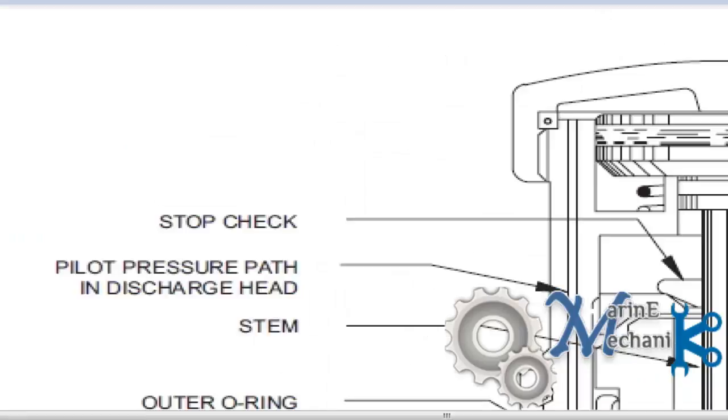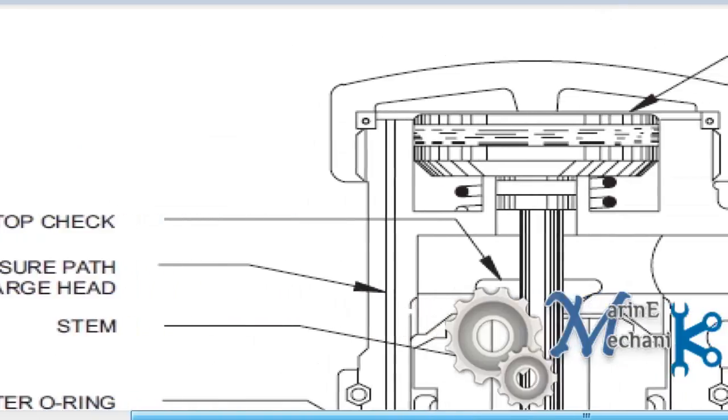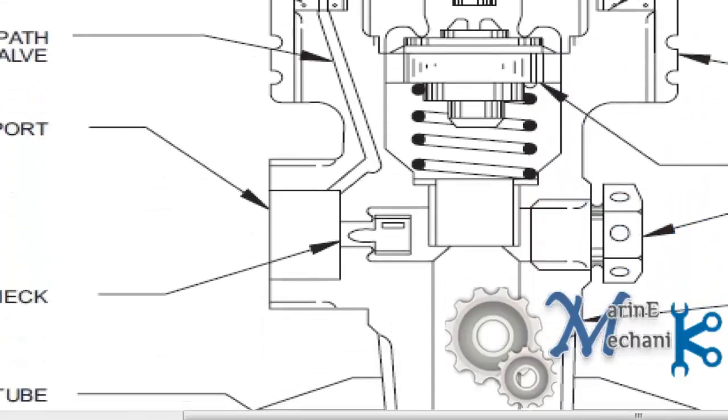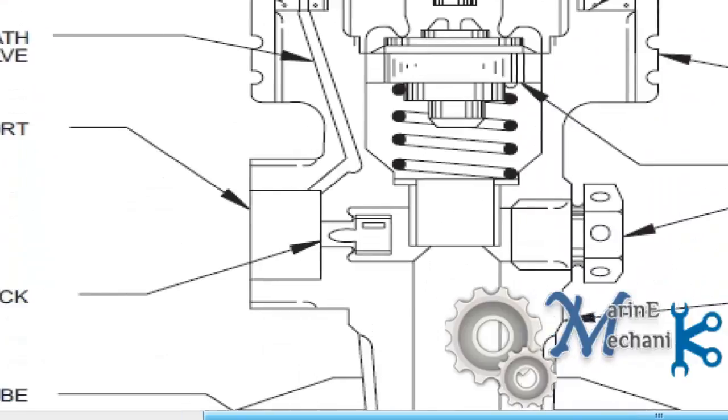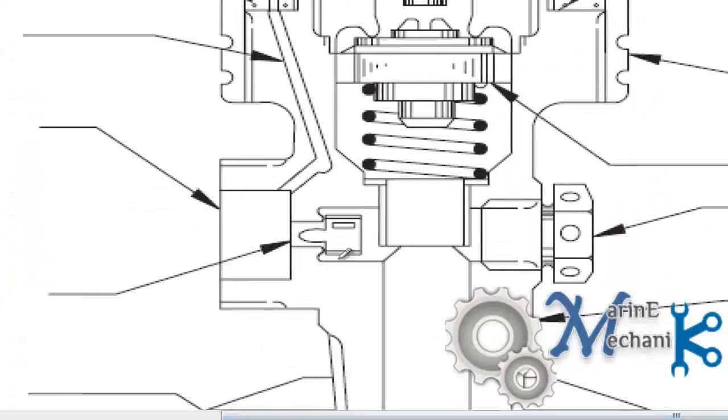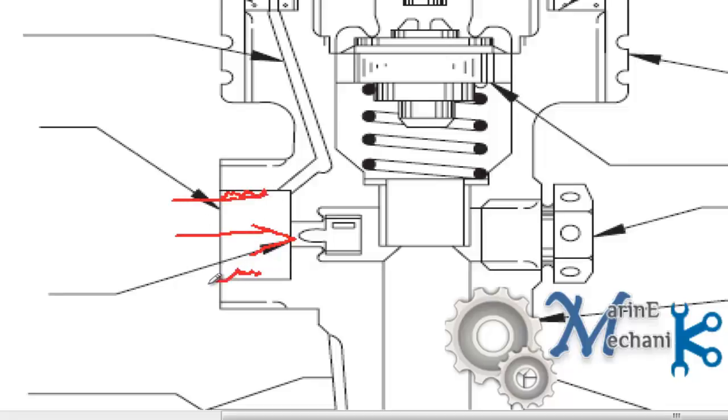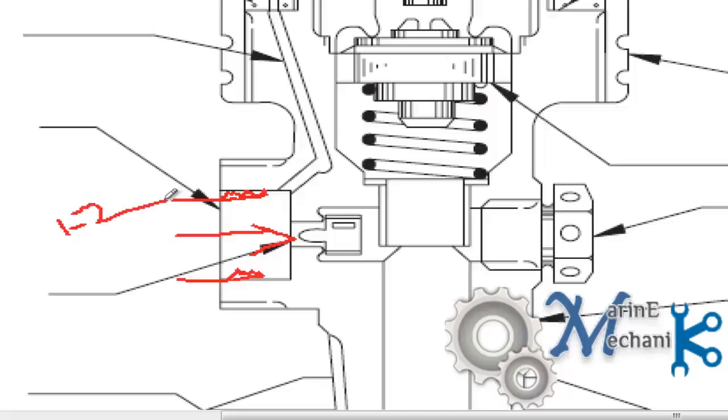I will enlarge it. This is the pilot check valve and here is a safety relief. Maybe a bursting disc or some spring loaded relief valve depending on the design. As you see here, here is the pilot inlet. It will be usually threaded in this space so that we can connect the ferrule of the CO2 pilot bottle and as you know the CO2 pilot bottle is roughly 1 to 2 kg. It is a small bottle.